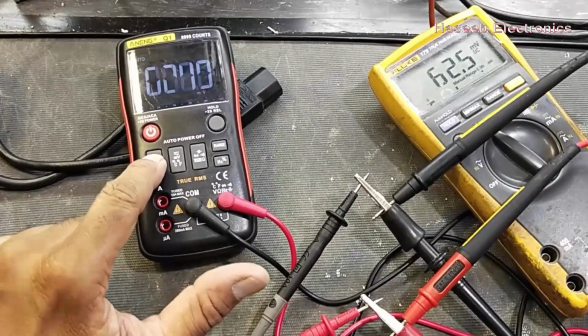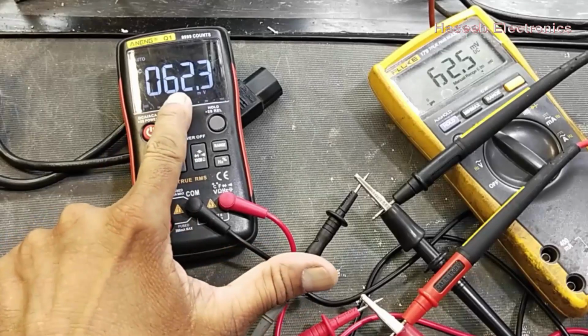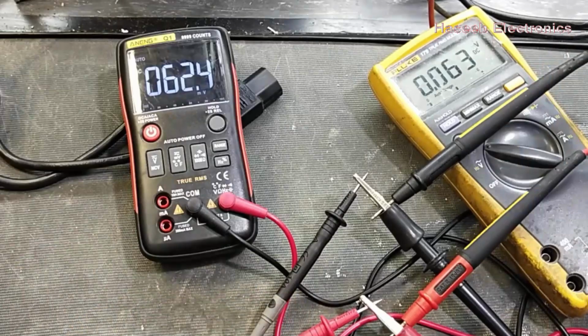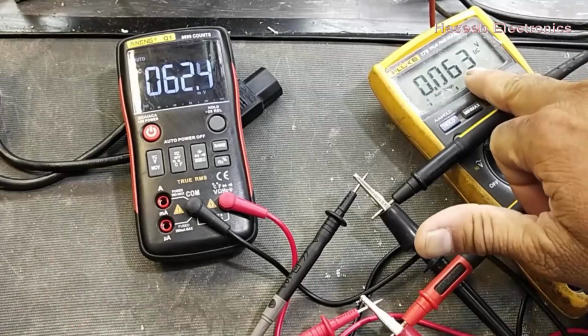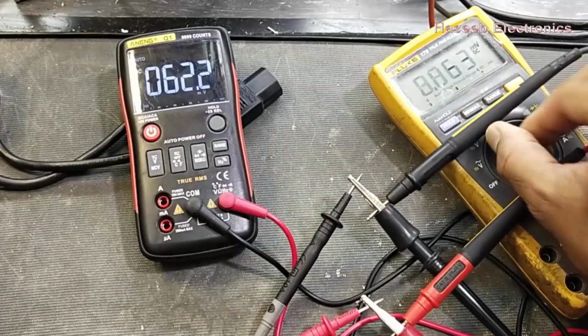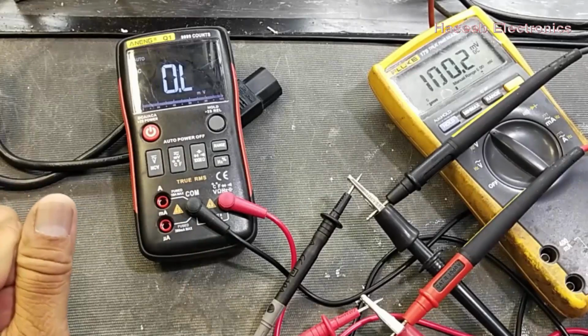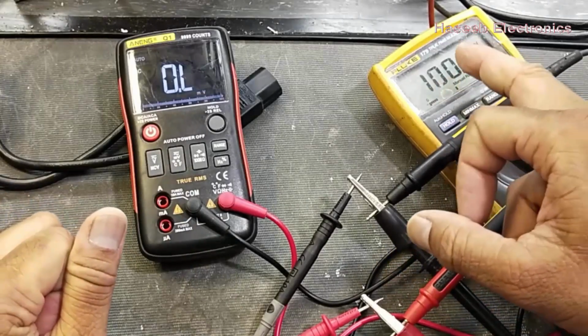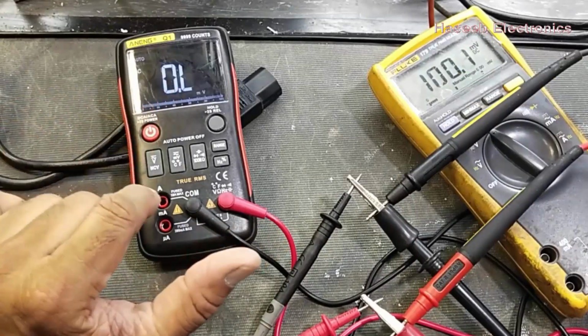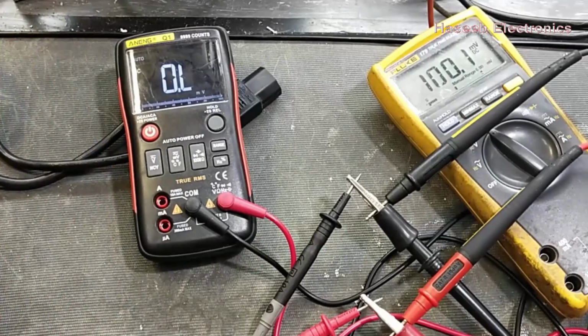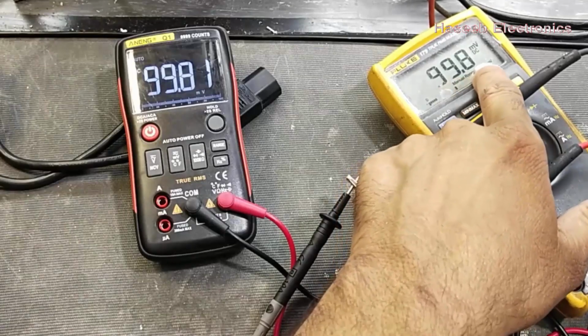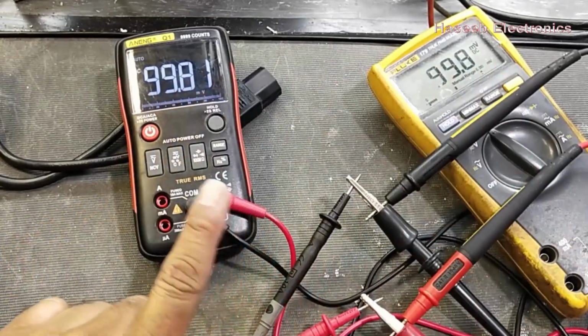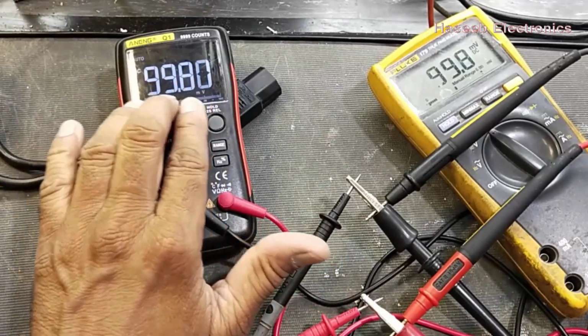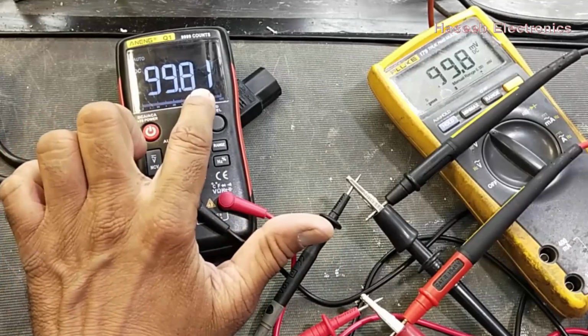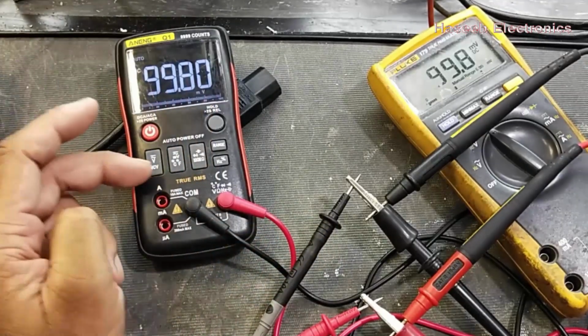And if we move to DC range, it is reading 62.5, and here 63 millivolt. So both multimeters are giving good readings. I applied a 100 millivolt signal. This multimeter is measuring 100 millivolt, but it displays overload. So it can measure 99.9 millivolts. So here I am getting 99.8, 99.8. When I apply 100 millivolts, it will say overload because it has a maximum range of 99.9 millivolt. That's very nice. After that we can shift to the DC voltage range.